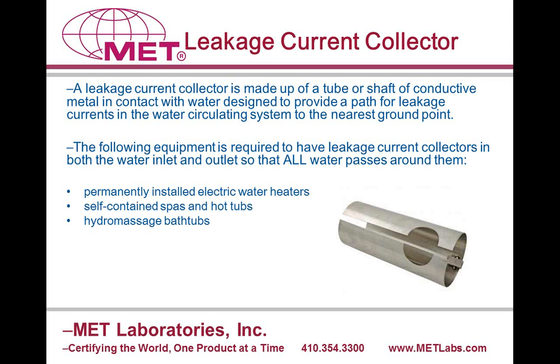The leakage current collector is a piece of copper or brass tubing or plastic tubing with a corrosion-resistant lug inside of it that all water passes through to provide a path to ground for all of the water that has come in contact with an electrical appliance. It gets installed in all of your water inlets, all of your water outlets. Again, it will be bonded to about 6 gauge wire to the main service ground. So as I said, a leakage current collector is very important in the design of your equipment, and it's absolutely necessary for water heaters, spas and hot tubs, and bathtubs with electrical appliances.